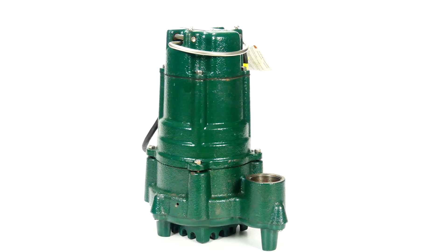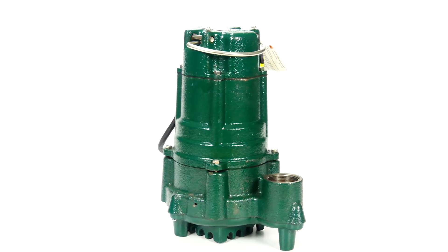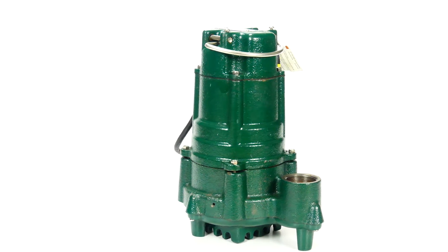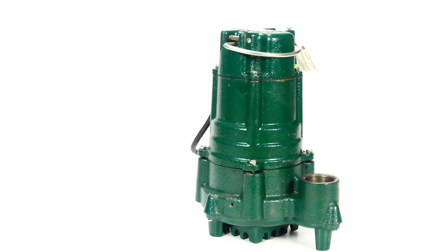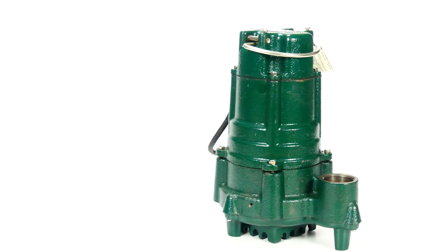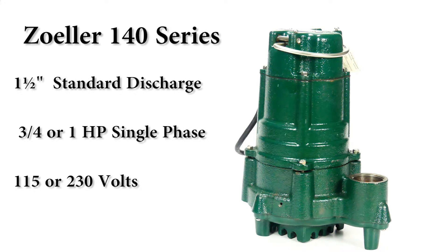The motor housing and volute receive a corrosion-resistant powder-coated epoxy finish. A one-and-a-half-inch discharge is standard with these pump models. The 140 series utilizes a three-quarter or one horsepower motor depending on the 140 or 145 model and is offered only in single phase in 120 and 230 volts.